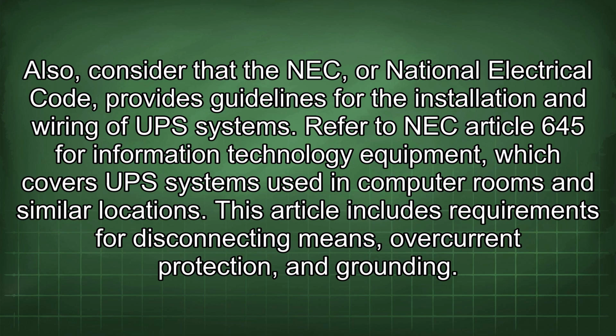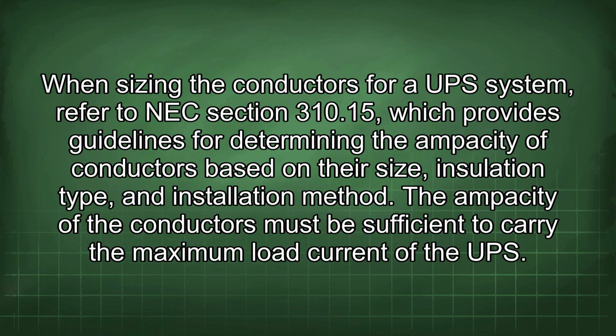Refer to NEC Article 645 for information technology equipment, which covers UPS systems used in computer rooms and similar locations. This article includes requirements for disconnecting means, overcurrent protection, and grounding. When sizing the conductors for a UPS system, refer to NEC Section 310.15, which provides guidelines for determining the ampacity of conductors based on their size, insulation type, and installation method. The ampacity of the conductors must be sufficient to carry the maximum load current of the UPS.